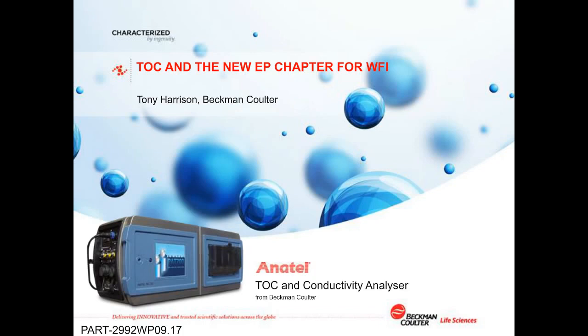Yes, so yeah, you're quite right. TOC events are often very short-lived, transient events. And of course, to get to root cause, it's important to capture a sample of that water whilst the TOC excursion is happening, in order to establish where the TOC spike may have come from. And that's why the PAT 700 from Beckman Coulter captures a sample of that water whilst the TOC event is actually happening.